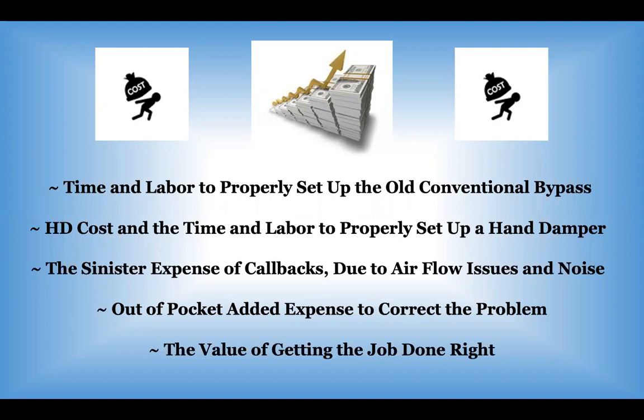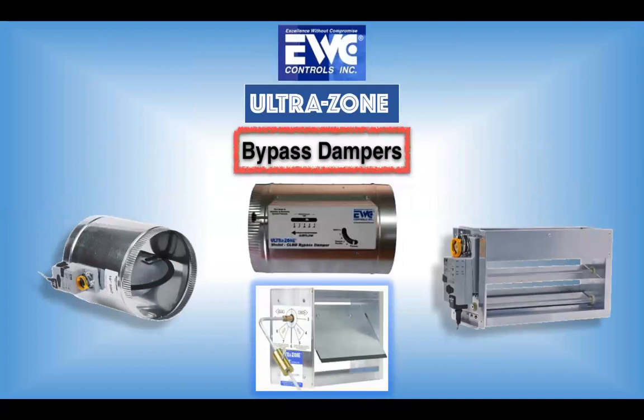And lastly, what's more value than to get the job done right? Have peace of mind that when you leave, I'm not going back on that system, and it will continue to operate properly going forward in any and all modes of operation. So you choose. You choose which damper you want to use. And by the way, you do not need a hand damper for the SBD. The SBD has a unique curve design with baffles on this blade that create the same type of restriction that a balancing damper does. No need to go through all of that.